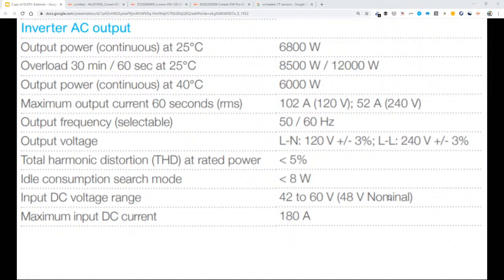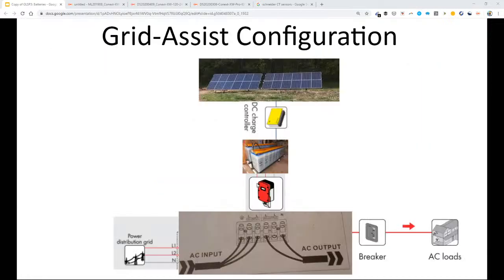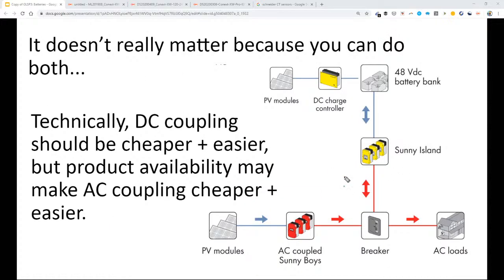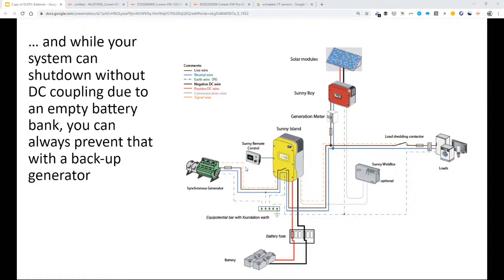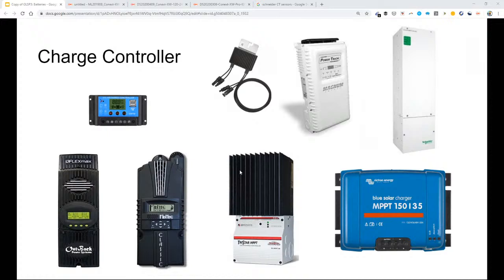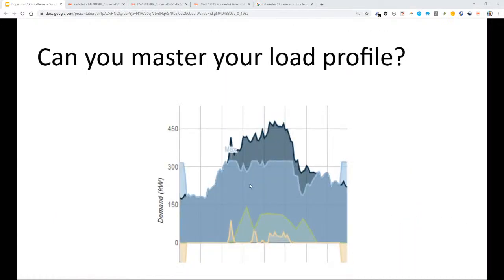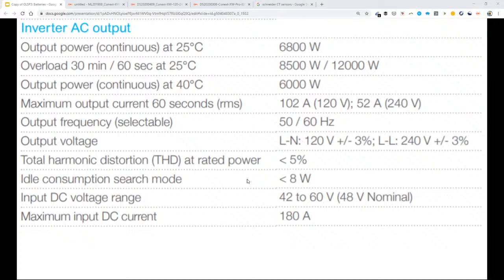What is not readily apparent about battery inverters that are two directional, that can charge from the grid and discharge to the grid, is they might actually have two different output ports, one for the grid coming in and one for the grid coming out. So it's not just like a two-way street that goes one way and the other. It's not like a solar array that has one set of wires connected to it. Of course, that solar array is just doing a one-way output from the array. It's not charging the solar array with current. And so battery inverters, even though they're bidirectional, they have a separate input from the grid and a separate output from the grid, and maybe even a third output for a critical load panel or backup load panel.